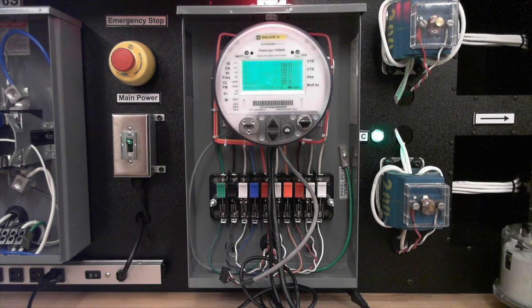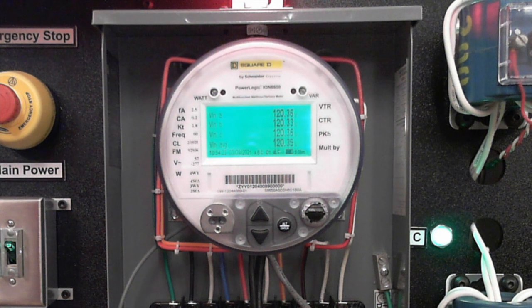Right now it's on the phasor view. So this gives us our voltage and current relationship. And usually if you see the current is leading or lagging the voltage, that is an indication that your power factor is low. There's also voltage trends, and your harmonic display is in the alternate mode.